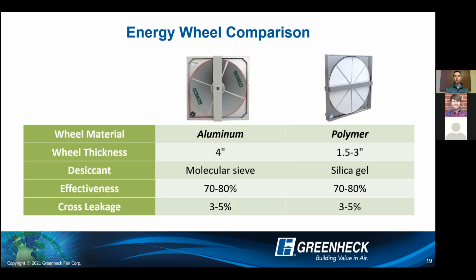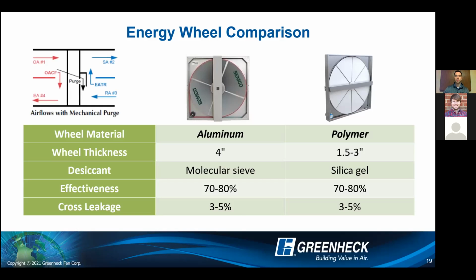Couple things related to cross leakage that I do want to touch on while we're talking about this. First one is going to be purge. We get asked a lot for purge sections, whether or not we have them, whether or not we recommend them, things like that. And really, I guess first what a purge does is it takes some more outdoor air to pressurize that purge section as you see. And what that does is it keeps that return air from actually crossing over and getting back into that supply airstream. So it does reduce that 3 to 5% to be a little bit lower, generally around that 1 to 2% range.